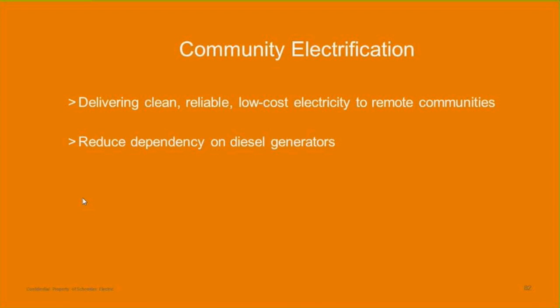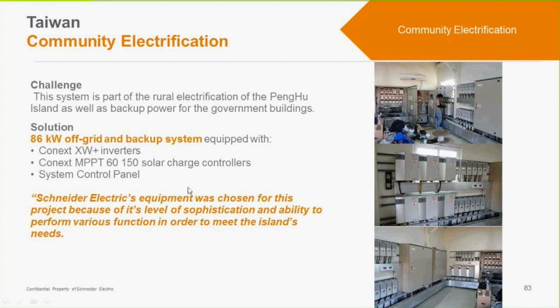It can be used for community electrification. Because these inverters can be set up in 3-phase configurations, you would have phase 1, phase 2, phase 3, and then they can be stacked, so you can get up to 102 kilowatt systems. In this case, they were using them as about an 86 kilowatt off-grid and backup system. And here's a few pictures on the side. You can see all of their charge controllers. Here's the XW Plus configuration. They have a whole power room set up.